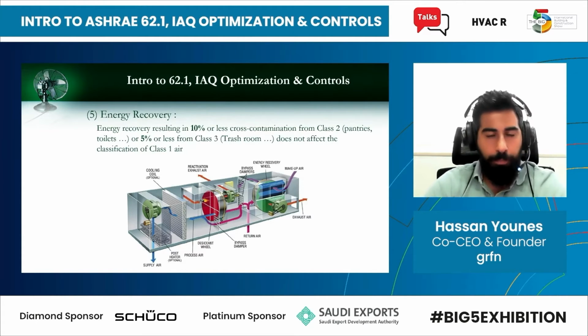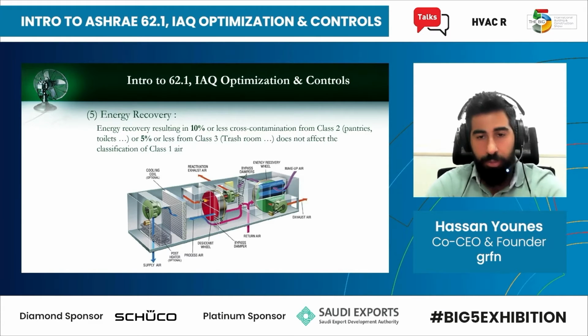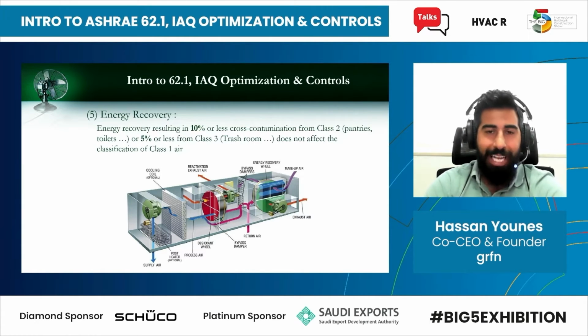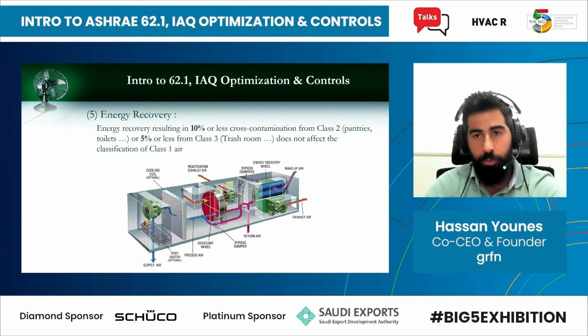Energy recovery: this is basically acknowledging the fact that energy recovery devices will have some cross-contamination between the exhaust and the outside air. And here it says that if the heat recovery is happening between exhaust air of class 2, so class 2 air is basically something coming out of a pantry or a toilet. Class 3 air, maybe air coming out of a trash room. So class 1 is like the best class, which has the lowest amount of pollutants and contaminants, whereas class 2, 3, and 4 become more and more loaded with pollutants, class 4 being the worst, and laboratory exhaust would be one of them.